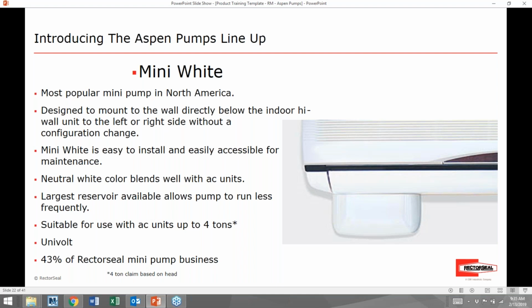Now, this pump is still capable of pumping 10 or 15 feet and operating on a 36,000 BTU unit or a 3-ton unit. The sweet spot for high wall units is somewhere in the neighborhood of 18 to 24,000 BTUs. So we typically are not going to have any trouble. And I would say that the Mini White is good for roughly 80% of applications out there. The Mini White is a univolt pump. It only comes in one SKU. And again, that univolt will allow voltage inputs from 100 all the way up to 250 and self-modulate everywhere in between. And like I mentioned, it is 43% of the RectorSeal business in the mini pump category.